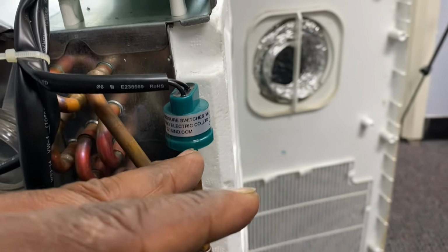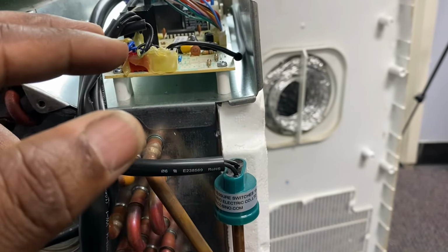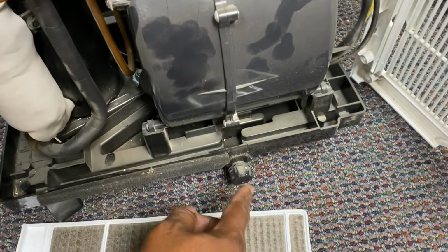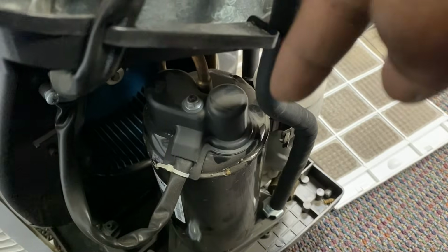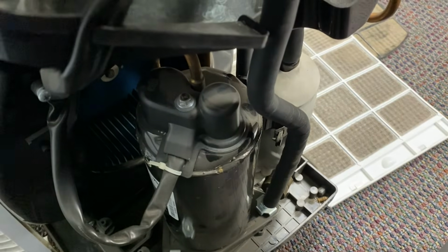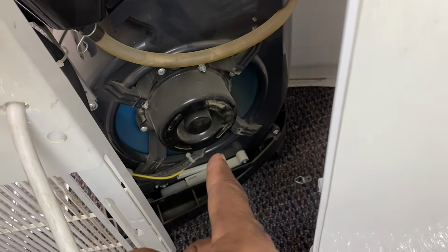This right here is a temperature sensor, and it gives a reading through the circuit boards, okay? And you can tell what it says on the LCD screen. If there's any fluid buildup, you can always drain it here. Just loosen that knob and that should drain. You can drain out any fluid there. And if it's a compressor issue, the compressor most likely is not starting or it's not heating up at all. If the fan's not spinning, it could be a motor issue.